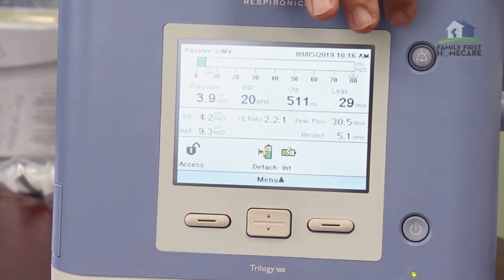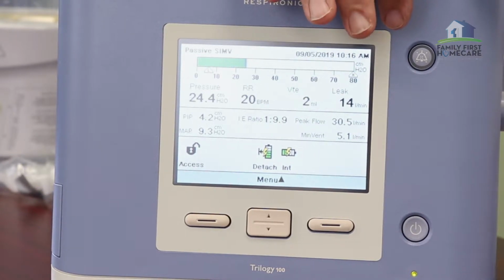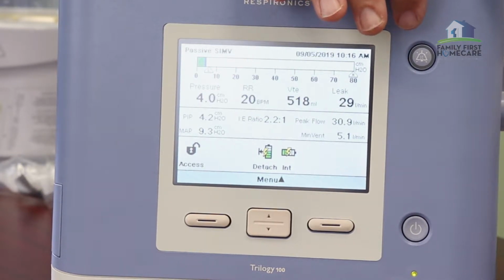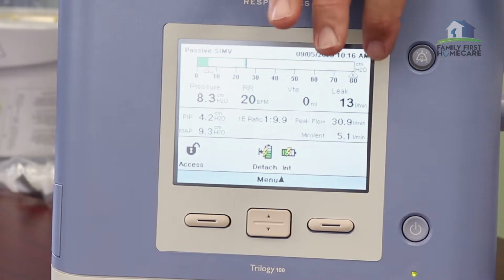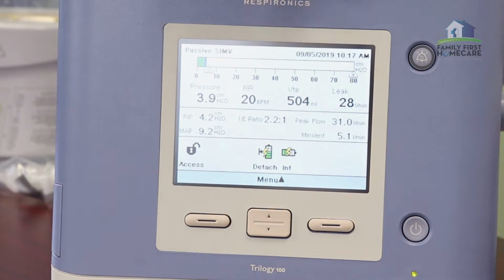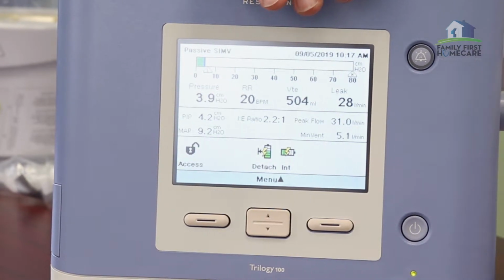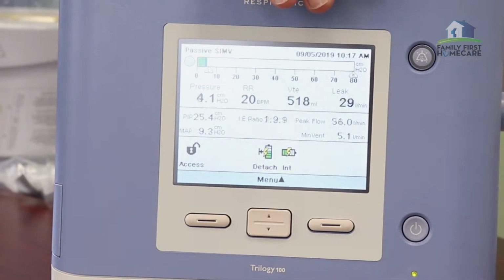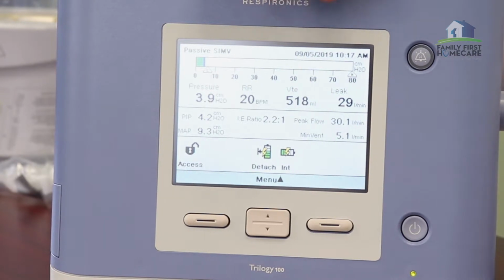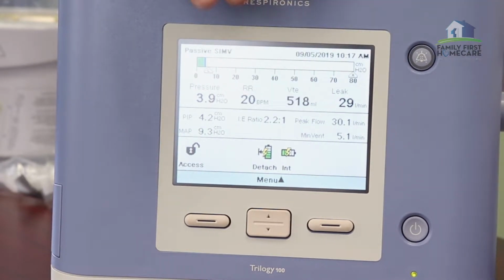The reason for that is, as you'll see in a little bit with the circuit, this is a passive circuit with a passive exhalation valve, which means there needs to be a leak, so that's quite normal. It can range anywhere from the upper teens all the way up to 50, so it really depends on how your patient is performing. Just record the number. Again, if it's all over the place, simply put a V.